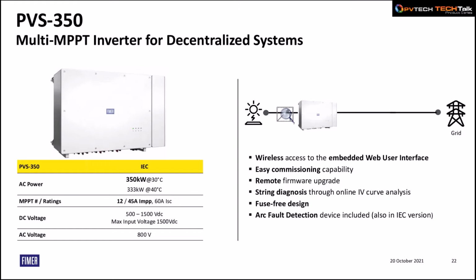So this is a perfect fit for the new applications which will benefit from the cost savings of the ultra high power modules. This is accompanied with a very large and very wide MPPT range, and as mentioned earlier, 800 volts AC in order to minimize AC losses. Combined with these basic features, we complement the product with additional and desirable features which are inherently available thanks to the multi-MPPT technologies.